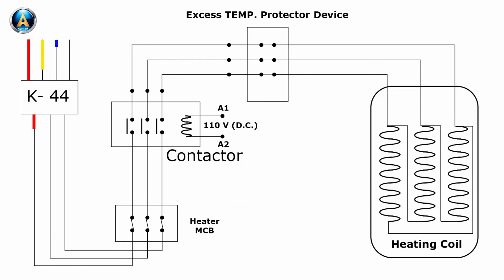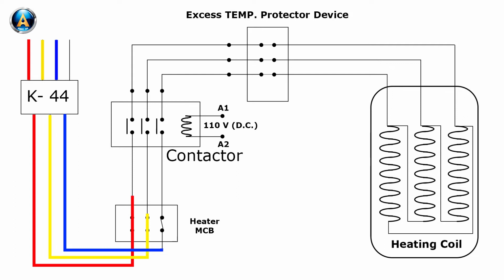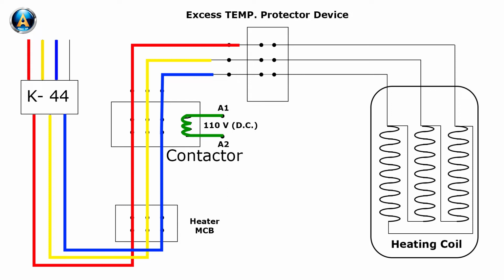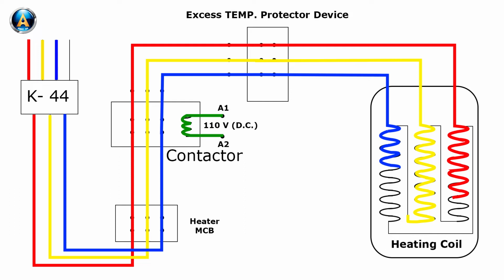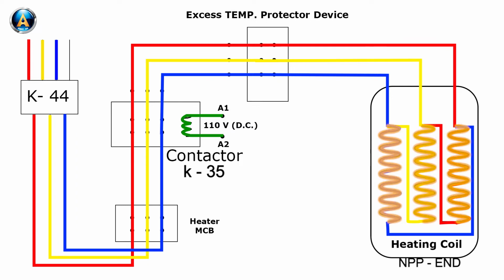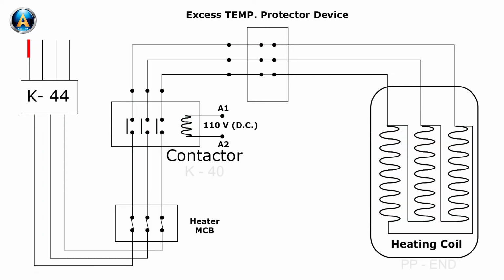Previously, 3-phase 415 volt AC power was available at the incoming of K35 contactor and also K40 contactor. After closing of the main contact, the heating coil of both become active like this. NPP end heater unit and PP end heater unit.